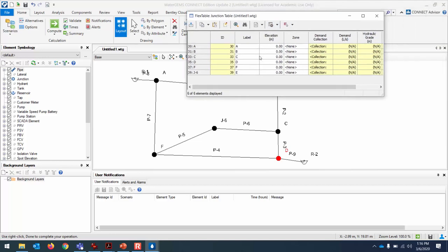None of these locations currently have an elevation. In this example they were all at the same elevation, so zero is fine. But in your project, elevations won't be zero — junctions are related to the contours on your map. Wherever you place your junctions in the network, look up the ground elevation there. The suggestion is to bury your pipe one meter below the ground, so enter the ground elevation minus one meter to ensure good cover on top of the water pipes.